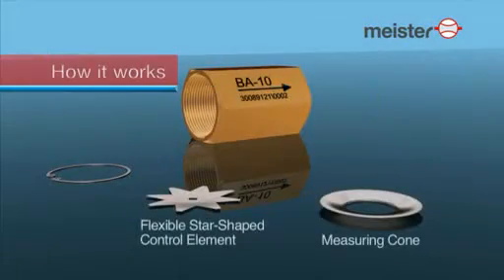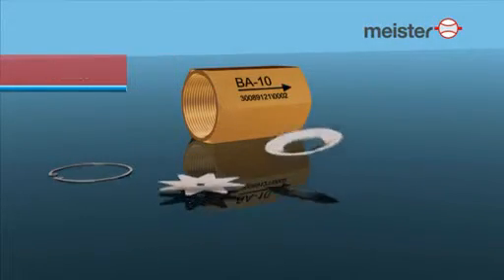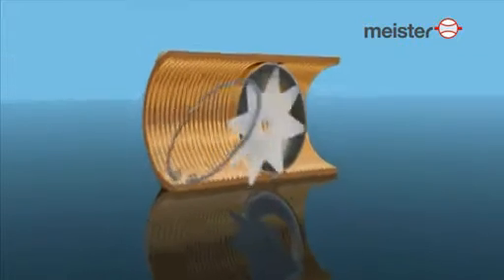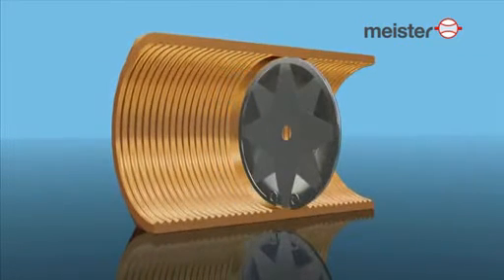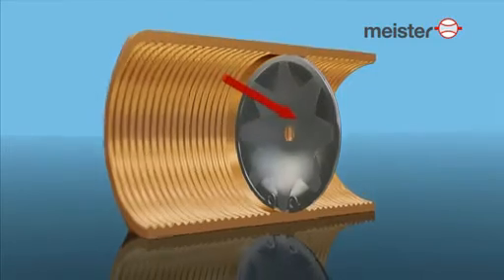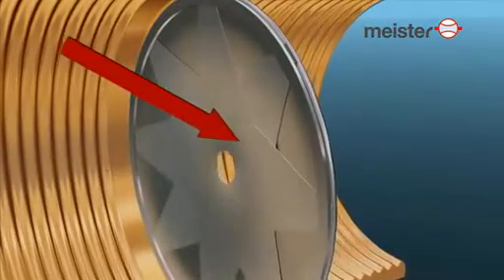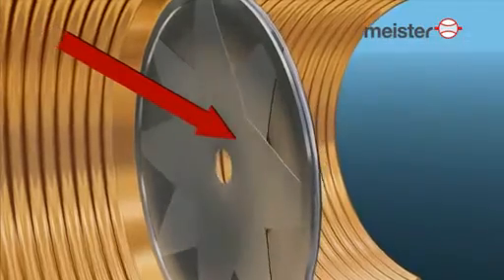The Meister flow limiter consists of a measuring cone and a flexible star-shaped control element. As the pressure differential increases, the control element is pushed into the cone, reducing the cross-sectional area. The flow rate remains unchanged.